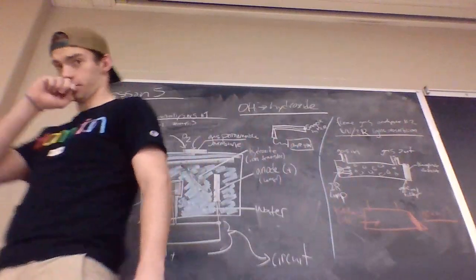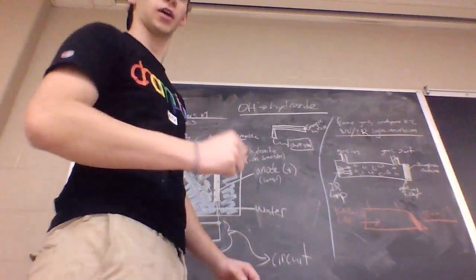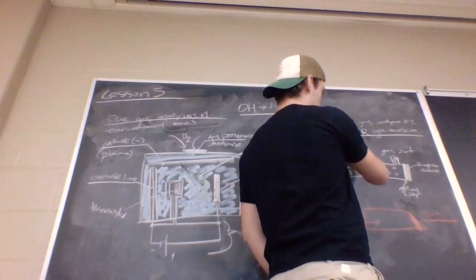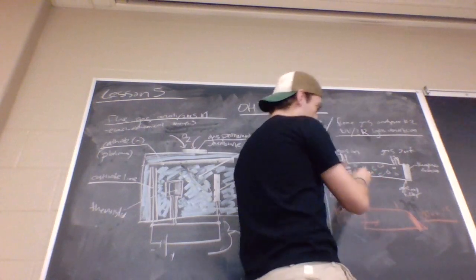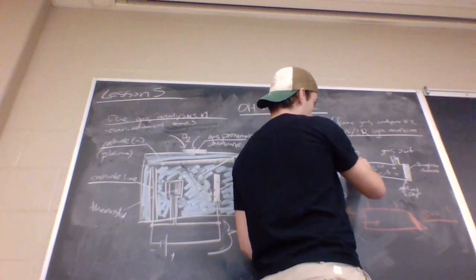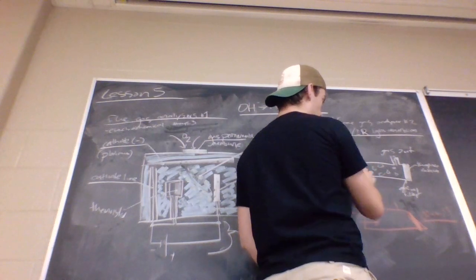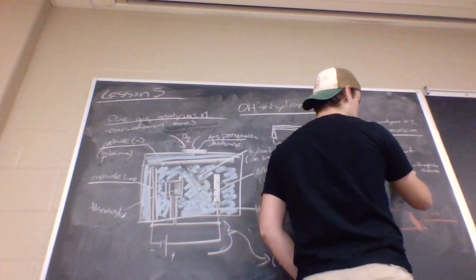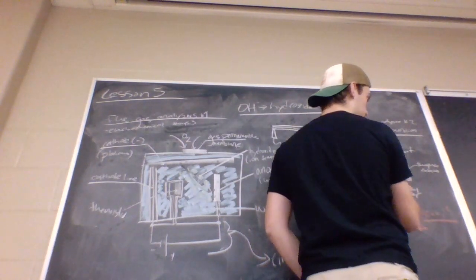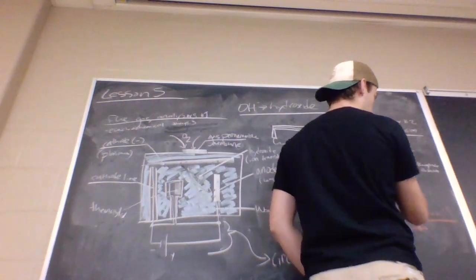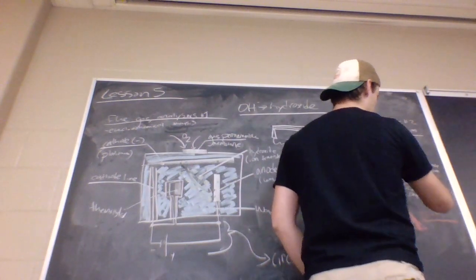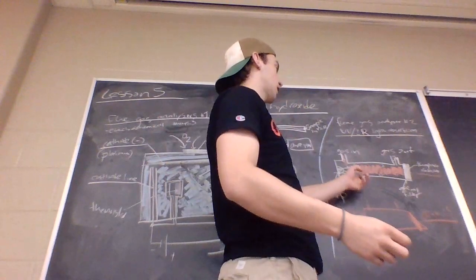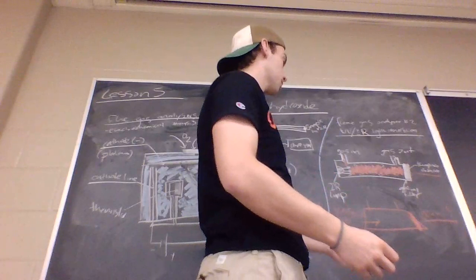Obviously, that's not the case, and the entire point is to measure gases. So we're going to have gas coming in, and when the gas is coming in, the gas is going to start to absorb some of that radiation. As it travels across, it's going to go through that optical filter for the specific wavelength of the gas, and it's going to be detected by the thermopile detector. Depending on how well that gas absorbs the radiation from that lamp, that's going to be less.